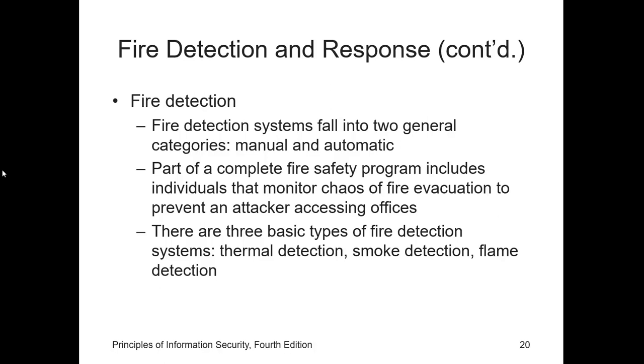The flame detector is a sensor that detects the infrared or ultraviolet light produced by an open flame. These systems require a direct line of sight with the flame and compare the flame signature to a database to determine whether or not to activate the alarm and suppression systems. While highly sensitive, flame detection systems are expensive and must be installed where they can scan all areas of the protected area.